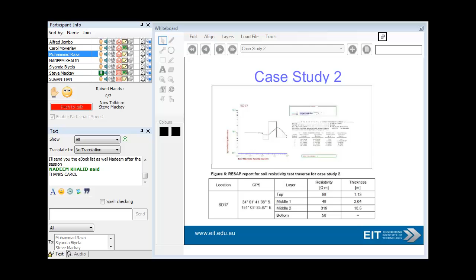So with this section here, you can see your top layer of earth, 98 meters with a thickness of 1.13 meter. As you go further down, the resistivity actually drops in the middle, probably it's got liquid or clay. Then right near the bottom, at 10 meters, it suddenly jumps again, probably rock. Then as you go further down, it drops to 58 meters, and that's the thickness going as deep as you can.